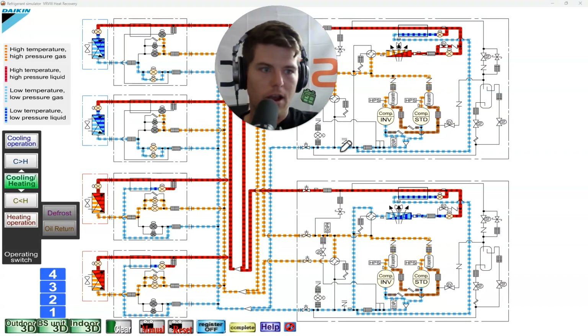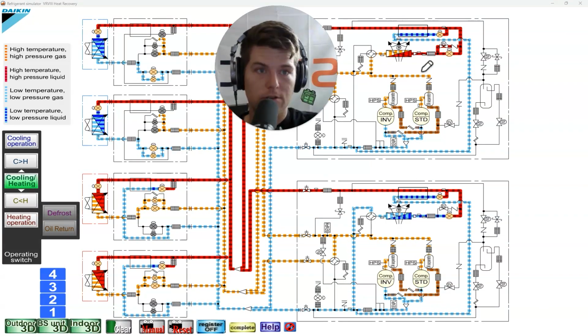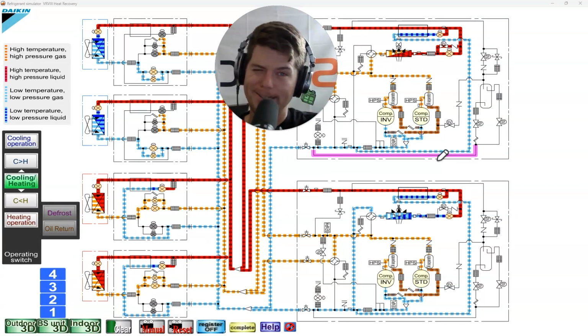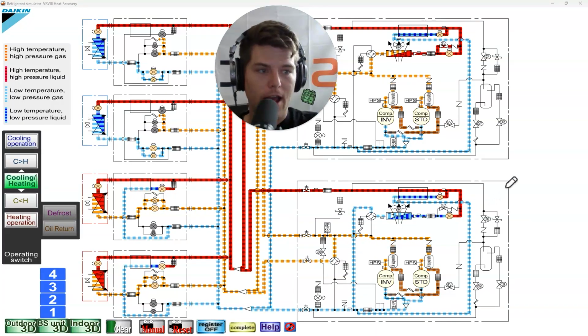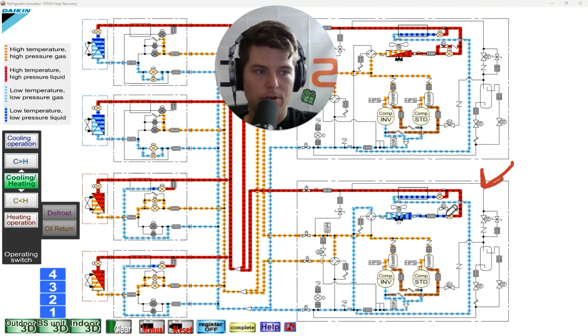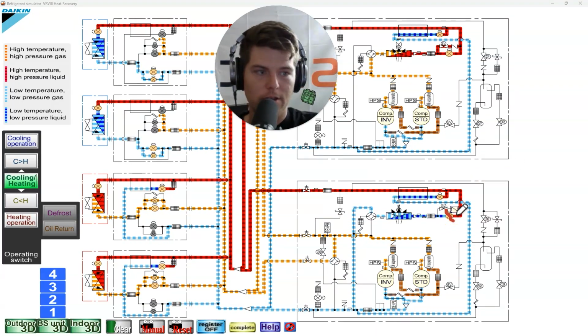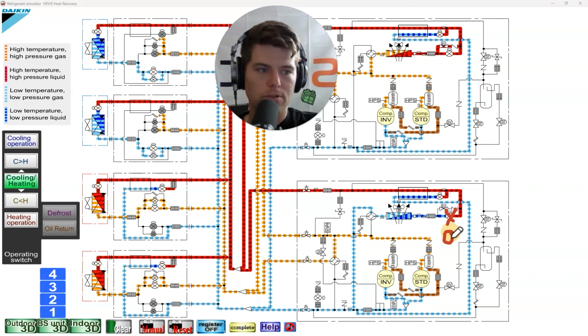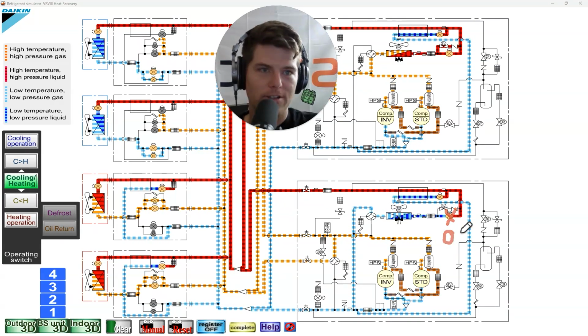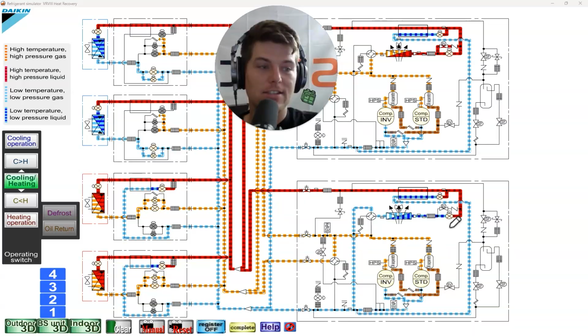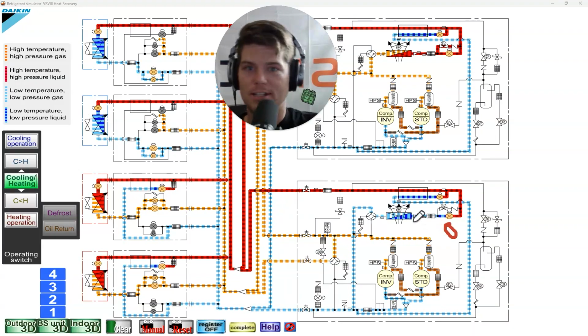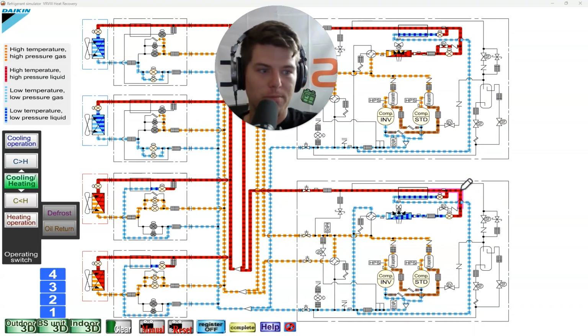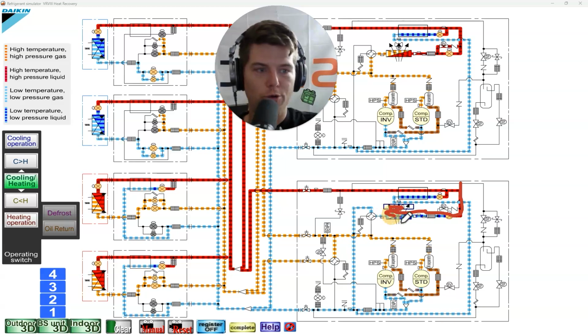Come on. All right. So this is cooling, heating, parallel operation. That's what we're in right now. This module is not being used, although it looks like it is being used. So guess what? This valve is at 0 pulses. Oh, look at that, XO. Heart and a kiss just for you. This is at 0 pulses. With it being at 0 pulses, what does that tell me? 0 pulses means there should be 0 flow through this coil.